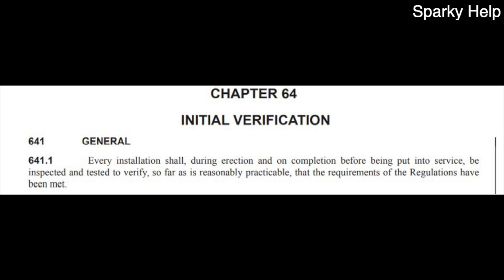What do we need to do? Well, every installation should, before being put into service, be inspected and tested so far as reasonably practicable. What does that basically mean? It means you should test it before you turn it on and make sure that it is in a fit working condition before energizing. So therefore do your dead tests. So which dead test do we actually do? Well, in this video we're going to do insulation resistance.